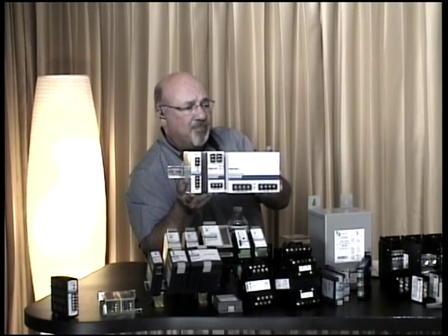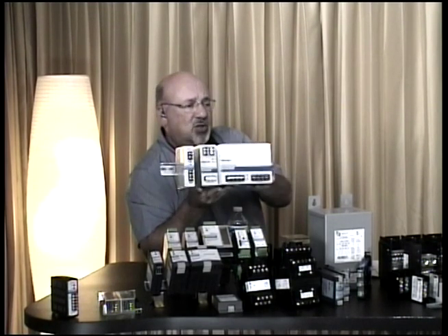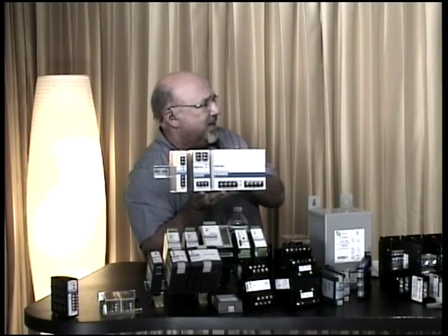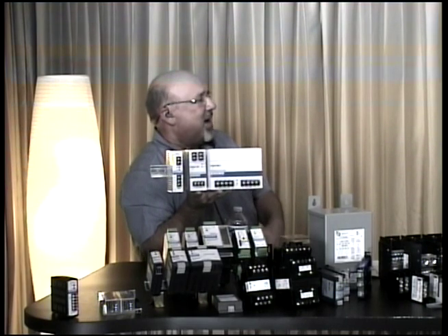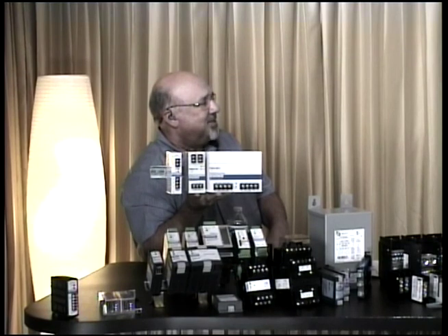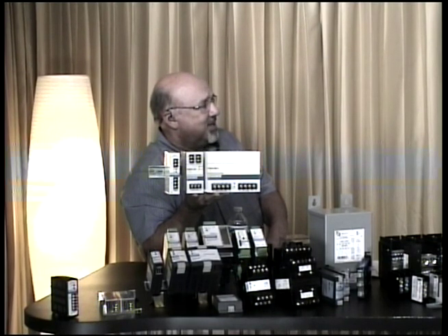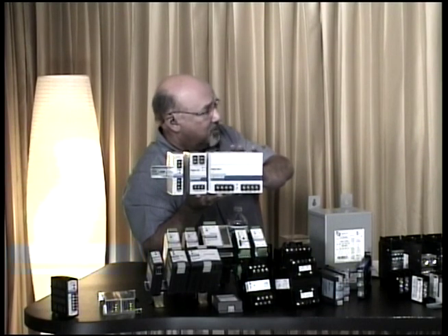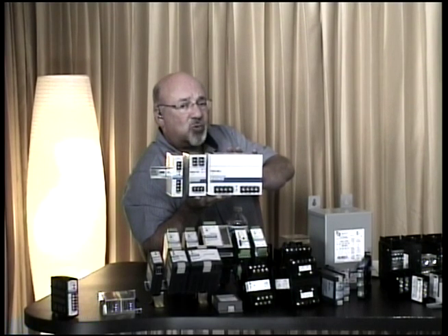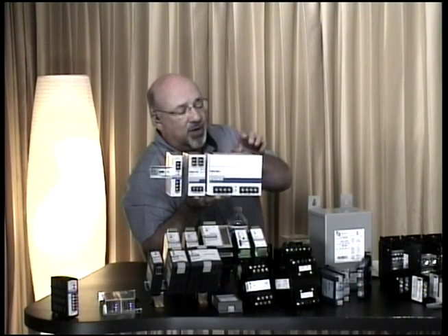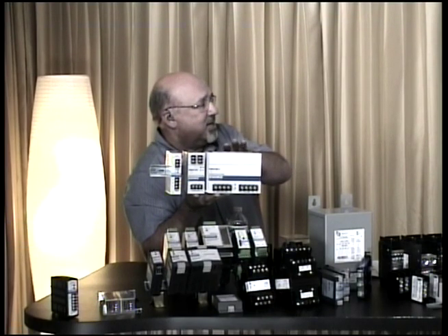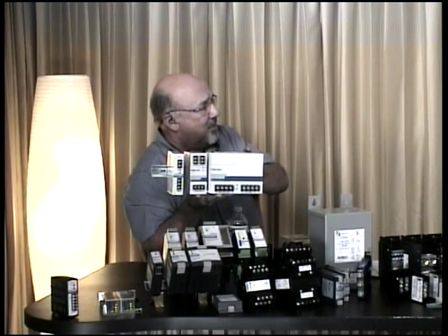Also in this line, we get into three-phase inputs, and that question comes up. Why would I want to use three-phase to power a DC power supply just to get DC out of it? One of the biggest reasons is it gives you a smaller form factor. If I bring 480 or 240 volt three-phase into my panel, and I'm able to take that three-phase and through fusing and secondary protection, I power my power supply.